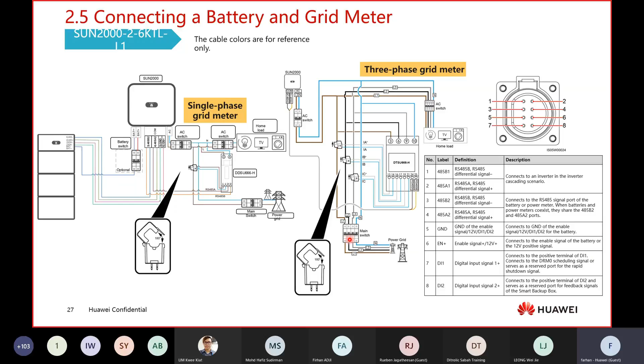So here is some guidance. You can see the CT here has a direction, meaning the CT current goes from the grid to the load. If you get the direction wrong, the DTSU will get the wrong information, because this is a bi-directional meter. For the pins we use on the single-phase inverter, the cascading uses pin number 1 and number 2. And for the meter, we use pin number 3 and number 4. Pins 3 and 4 will be connected to the meter.